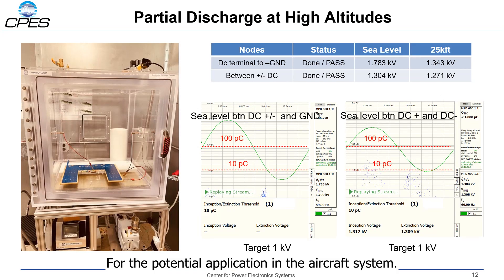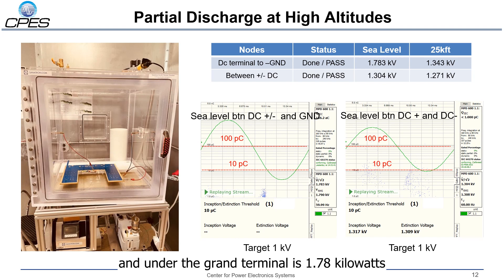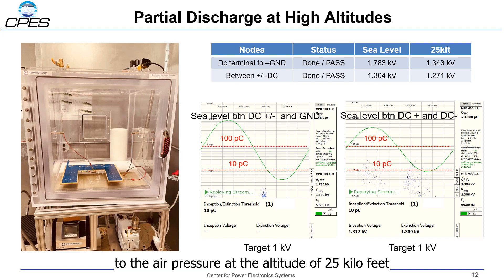For the potential application in aircraft systems, we are considering partial discharge at high altitude. We did some partial discharge testing in the low pressure chamber in our lab. At sea level, the partial discharge inception voltage (PDIV) between the DC terminal and the ground terminal is 1.78 kV. If we reduce the air pressure to the air pressure at an altitude of 25,000 feet, the PDIV decreases to 1.3 kV, but it still meets the requirement of our system.